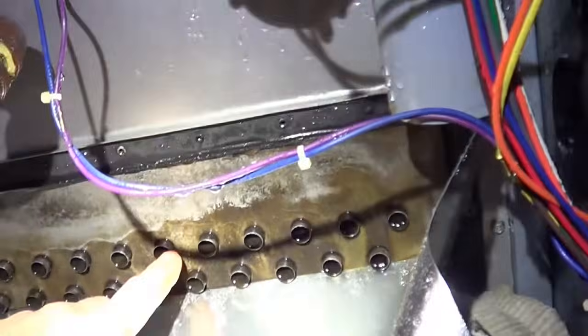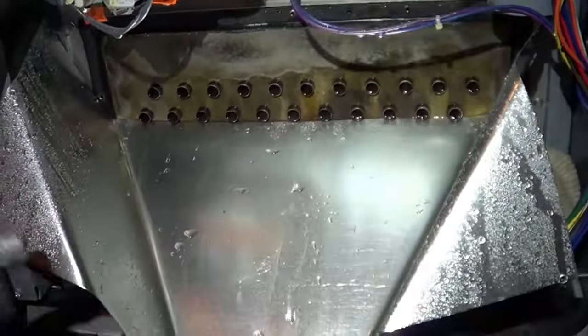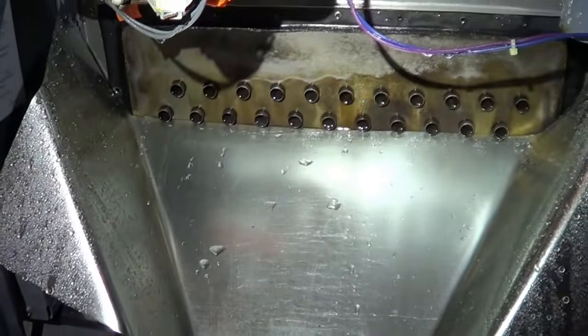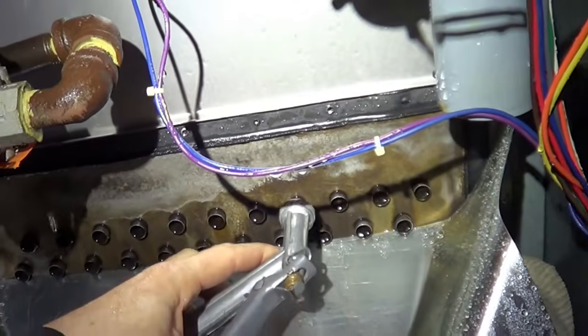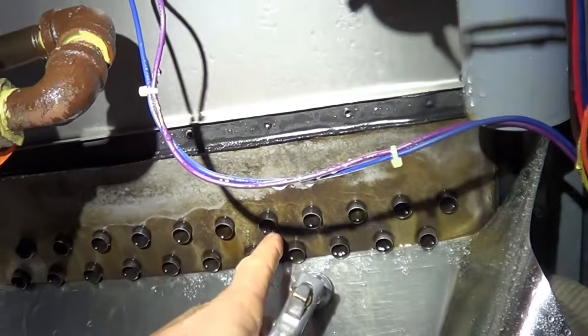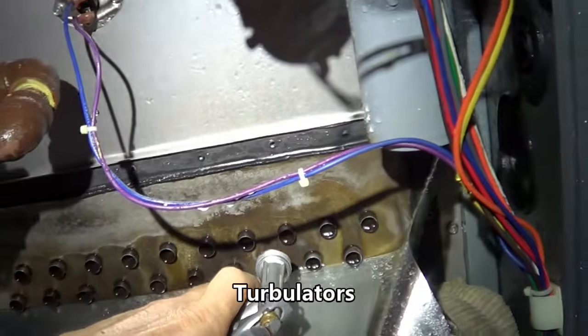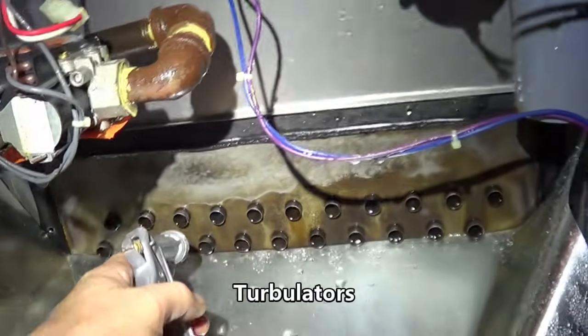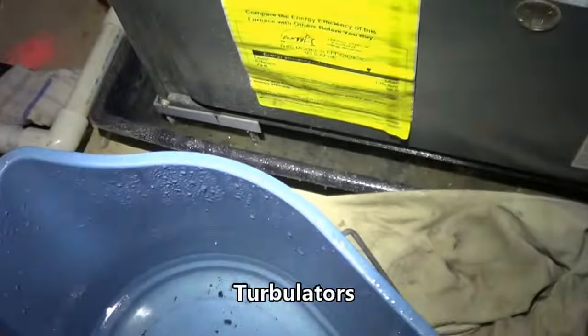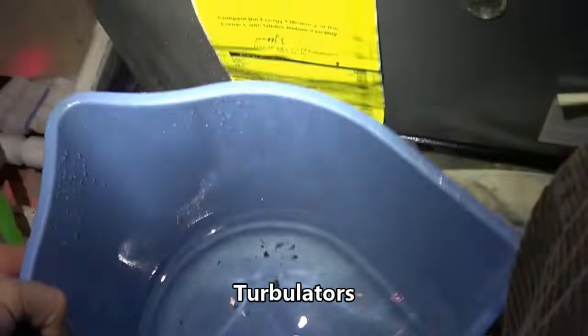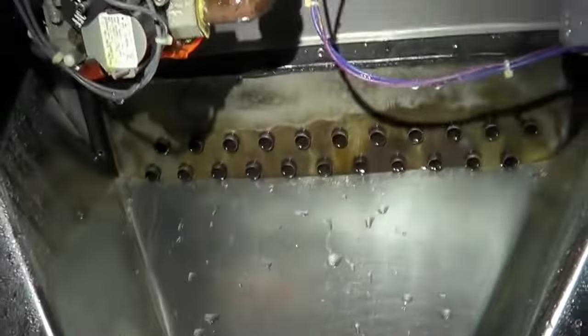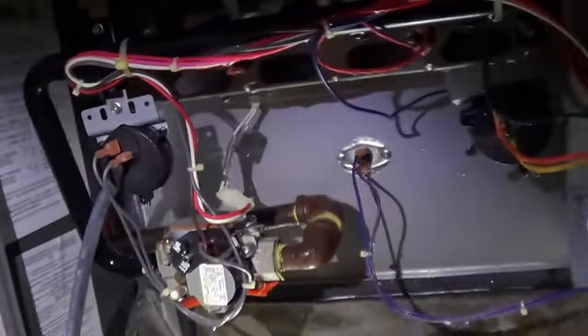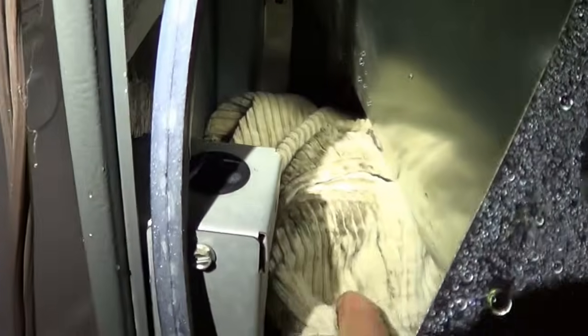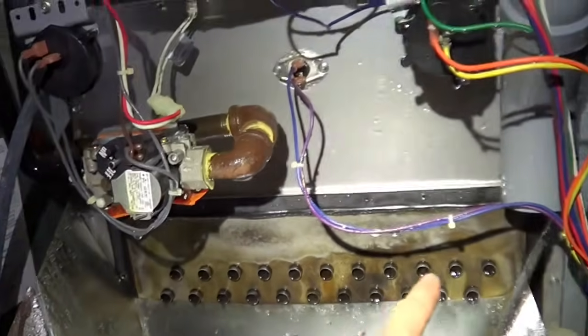Cleaning the secondary heat exchanger tubes. On this furnace, it's easy to put a gutter here to catch the water, and then I'm just basically blasting each tube. After removing the turbulators, I got a clean shot where I was able to clean all the tubes with the water hose, drain into the bucket, and the buckets actually started getting clean water. It was really nasty at first. I didn't video because water was splashing everywhere, and then I got a towel underneath here catching the water that I miss. So the secondary heat exchanger is clean.